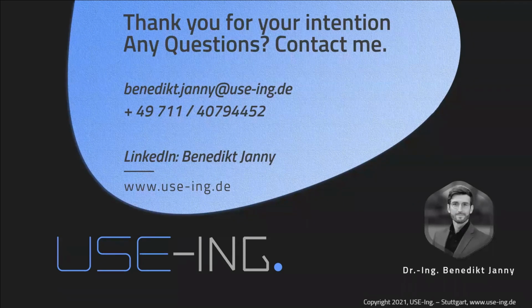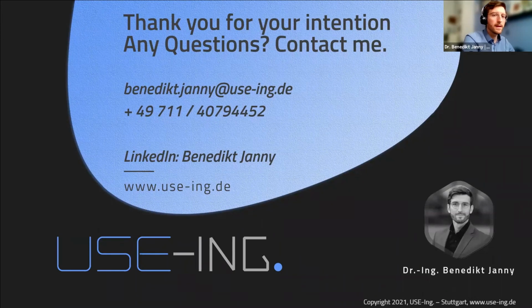If you don't have a prototype, that shouldn't prevent you from starting to think about the use context. Exactly. And a lot of people perform formative user interface evaluations on the way. Even if just two developers are sitting together discussing sketches, this is a formative user interface evaluation. Document it, write it down, and add it to your usability engineering file.